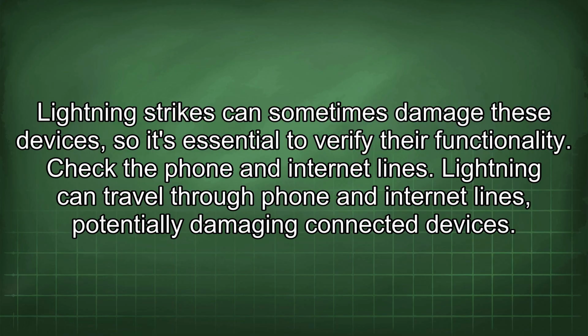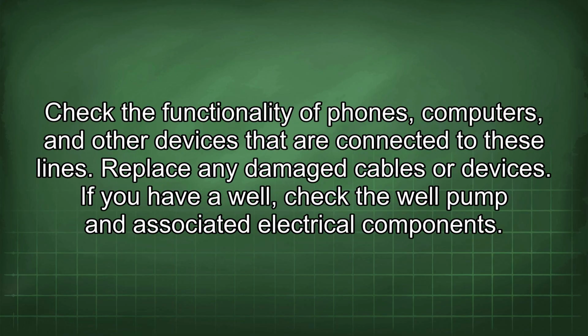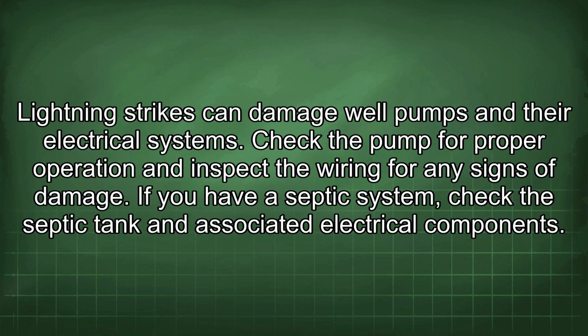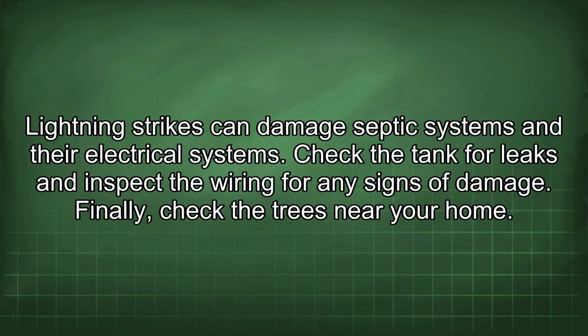Check the phone and internet lines. Lightning can travel through phone and internet lines, potentially damaging connected devices. Check the functionality of phones, computers, and other devices that are connected to these lines. Replace any damaged cables or devices. If you have a well, check the well pump and associated electrical components. Lightning strikes can damage well pumps and their electrical systems. Check the pump for proper operation and inspect the wiring for any signs of damage. If you have a septic system, check the septic tank and associated electrical components. Lightning strikes can damage septic systems and their electrical systems. Check the tank for leaks and inspect the wiring for any signs of damage.